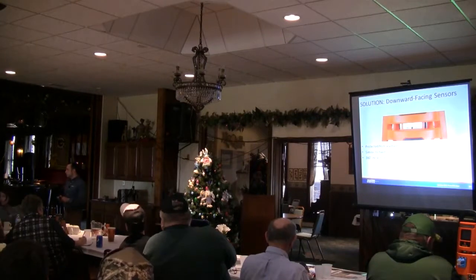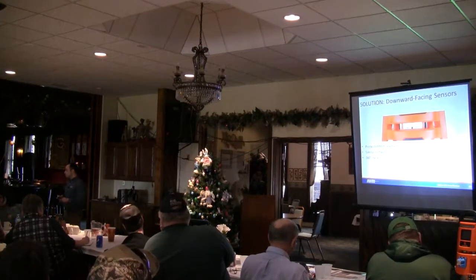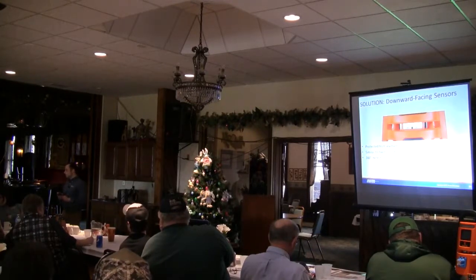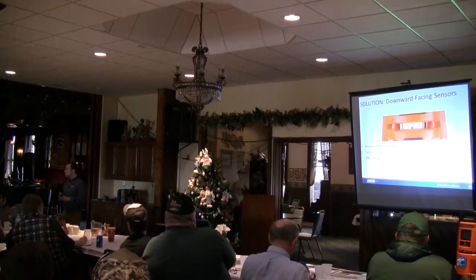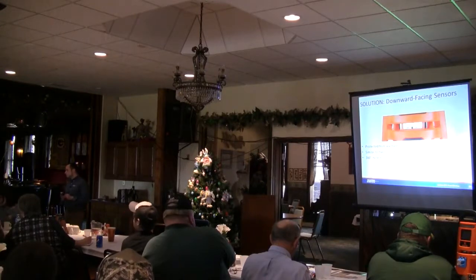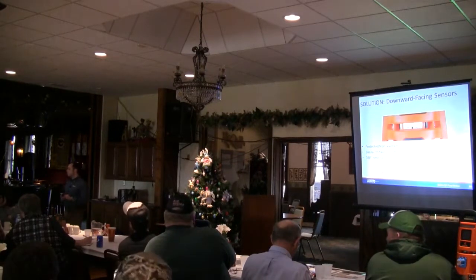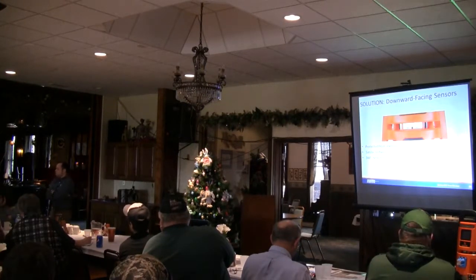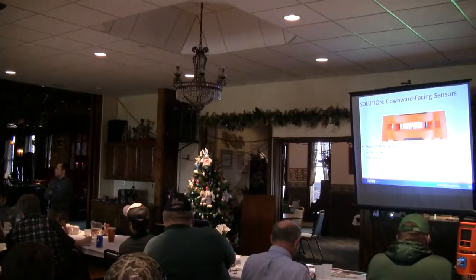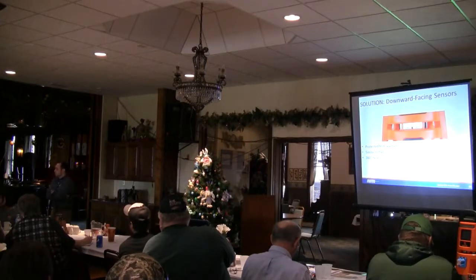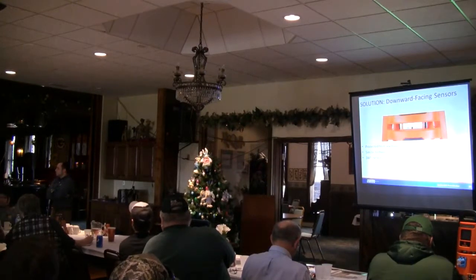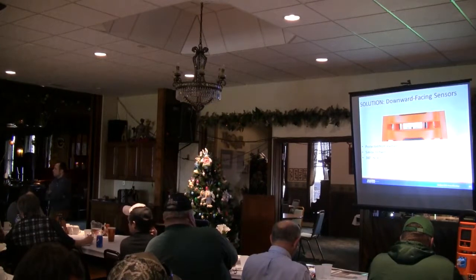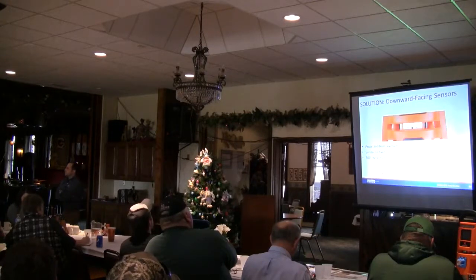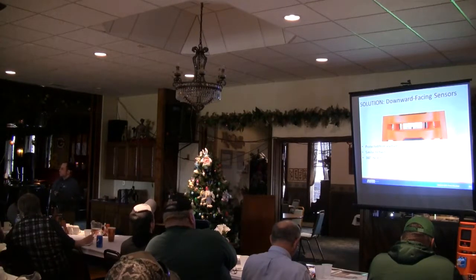Yeah. I'll acknowledge that when we were on site last fall, one of the monitors that we were using was a 4-gas monitor, and it was not this brand, it was a different brand, the MSA brand, and it was going off frequently because we had it pretty close to the pit opening, and we weren't even able to get a full day's use out of it because the levels were above 10 parts per million, and we decided conscientiously that we were going to raise the set points because we had another monitor that was still available and showing things, but this one was just really going off a lot because it was doing the 8-hour accumulation, it was doing the real time, it was just constantly annoying me. So we did reset that alarm knowing that moving the set point from 10 to 25, we didn't move it up to 100 or anything like that.